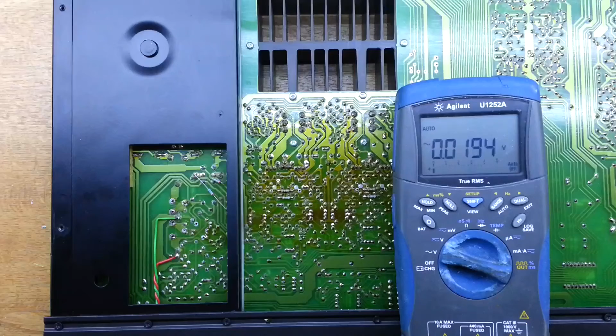So we'll just check the secondary windings, the secondary voltage on that, make sure they're where we want to be. I've got 32 on one side, and I've got 32 on the other side. So that's good - we're comfortable that the transformer's in good shape, and we'll go off now and find a replacement for that rectifier and see if that lets us fire up the unit.